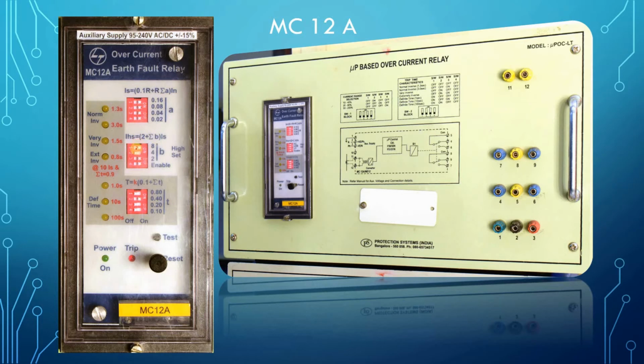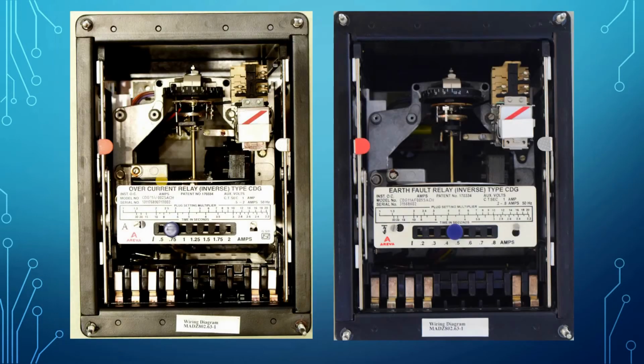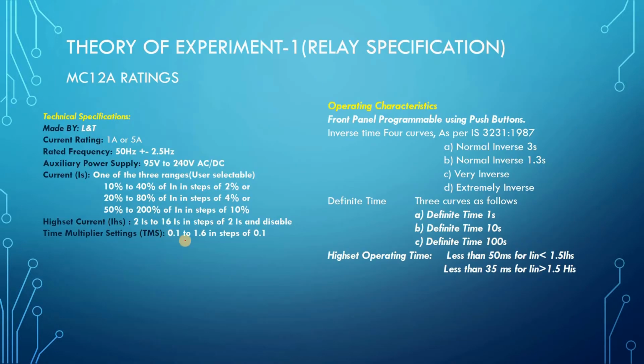The maximum IHS will be how much? 8 plus 2 is 10, plus 4 is 14, plus 2 is 16. So the maximum IHS can be 16. The minimum can be 2. 2 times IS minimum, 16 times IS maximum. As I told you, here it is written IHS 2 IS to 16 IS, and also the option of disable or enable.